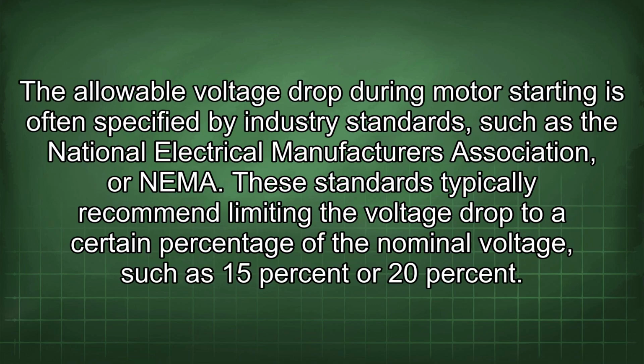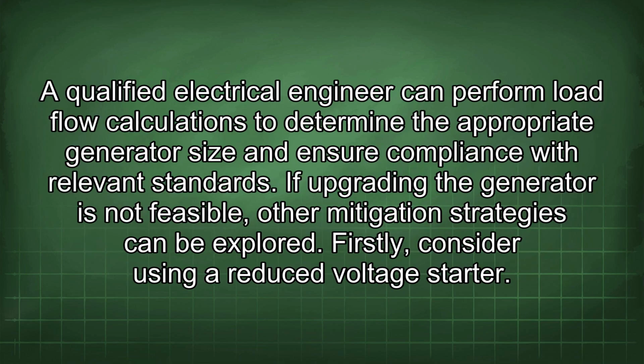The allowable voltage drop during motor starting is often specified by industry standards such as the National Electrical Manufacturers Association, or NEMA. These standards typically recommend limiting the voltage drop to a certain percentage of the nominal voltage, such as 15% or 20%. A qualified electrical engineer can perform load flow calculations to determine the appropriate generator size and ensure compliance with relevant standards. If upgrading the generator is not feasible, other mitigation strategies can be explored.